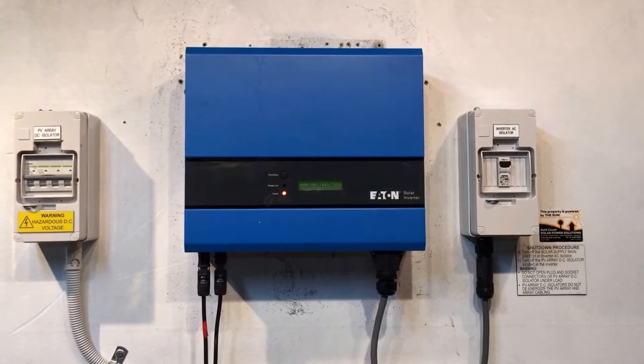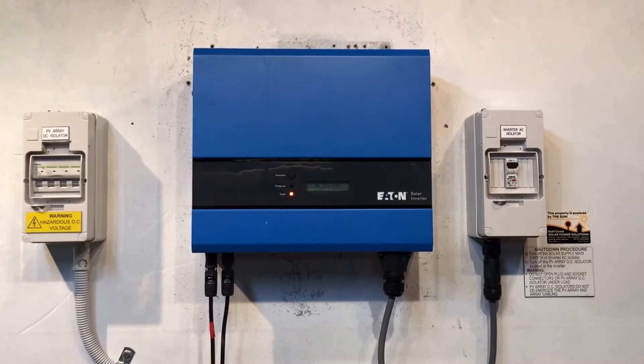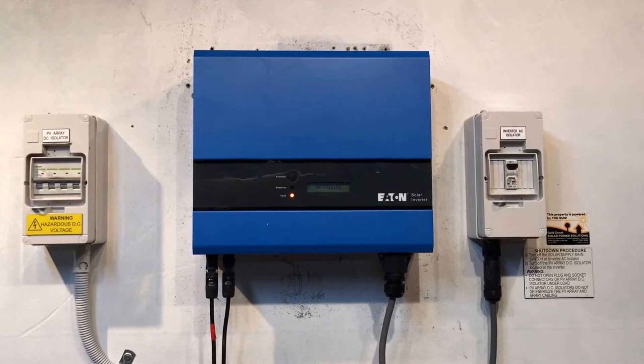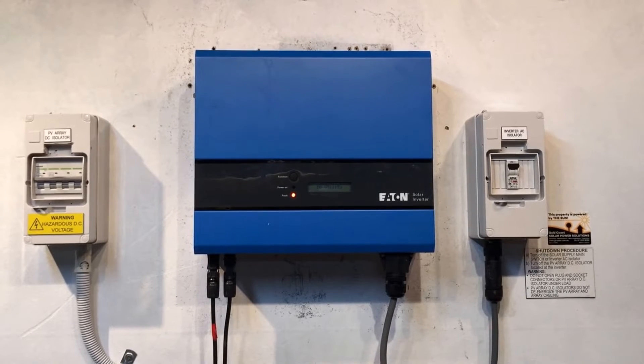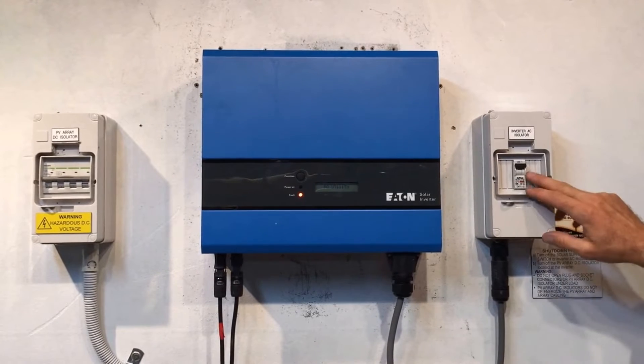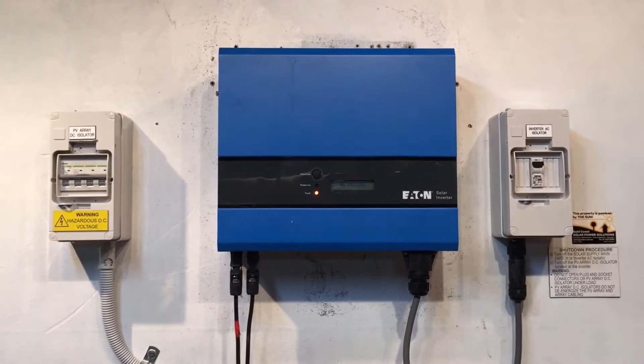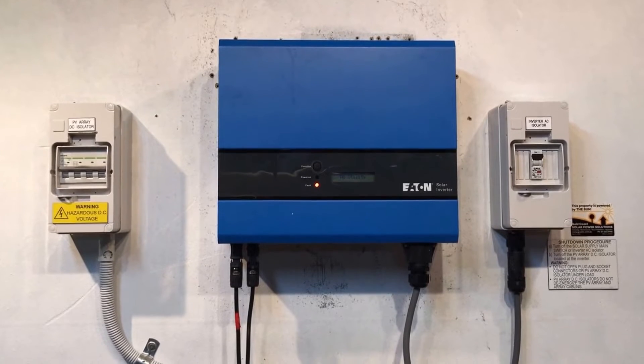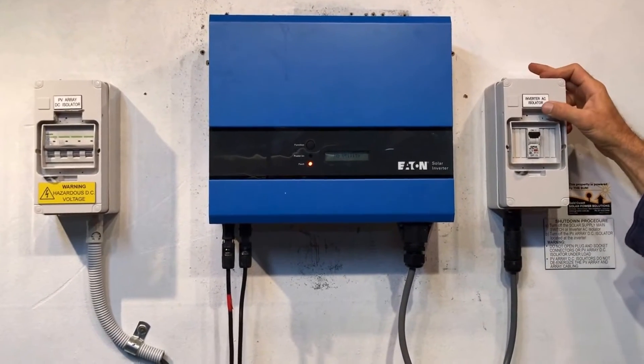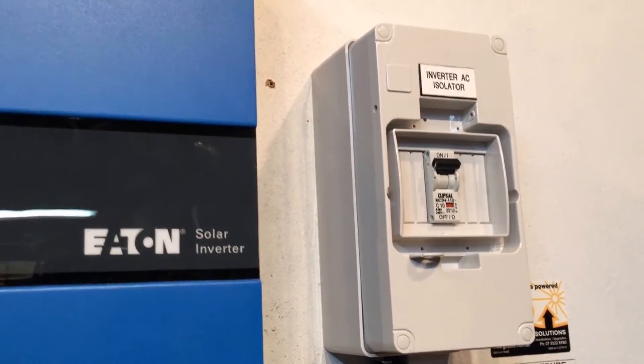No utility with an Eaton inverter means it's not detecting any power from the electricity grid, so there are a few things you want to check straight away. In your switchboard there should be a switch marked 'solar supply main switch' — you want to make sure that's turned on, which is usually a circuit breaker, and up is usually on. If the inverter has one of these inverter AC isolators, just make sure that's turned on, just like this one — it's in the on position there.